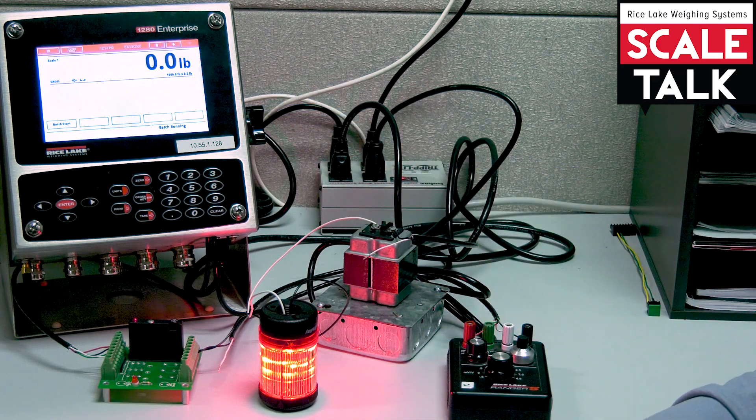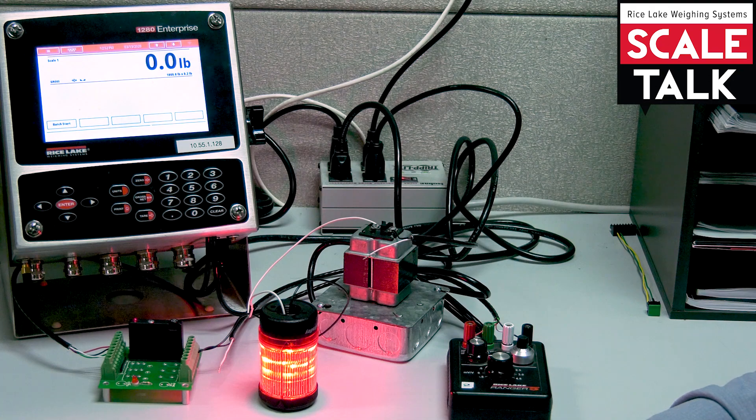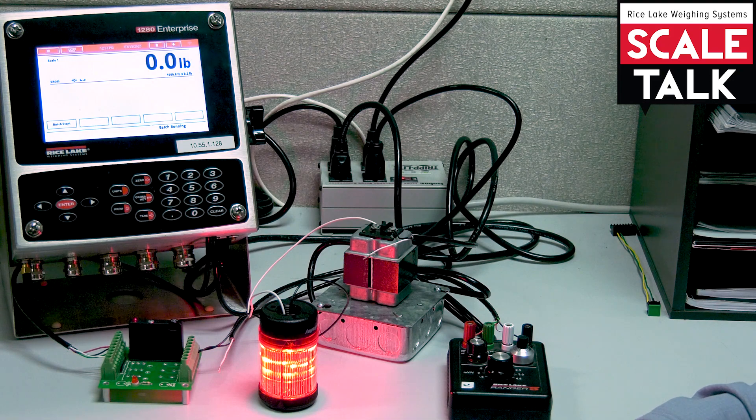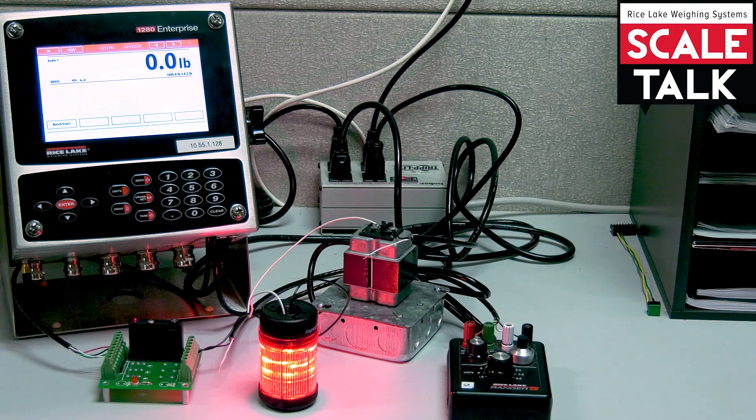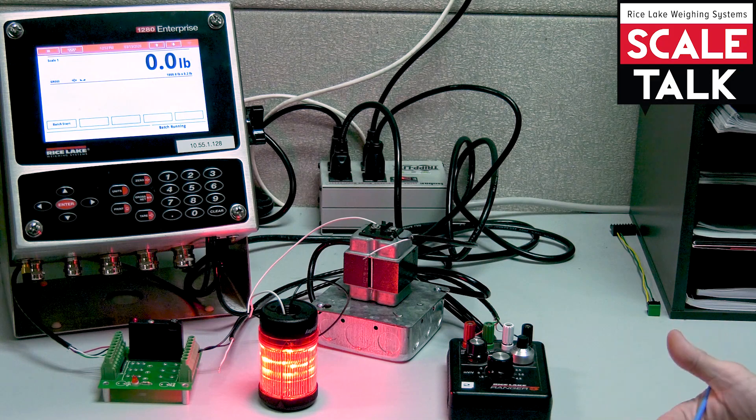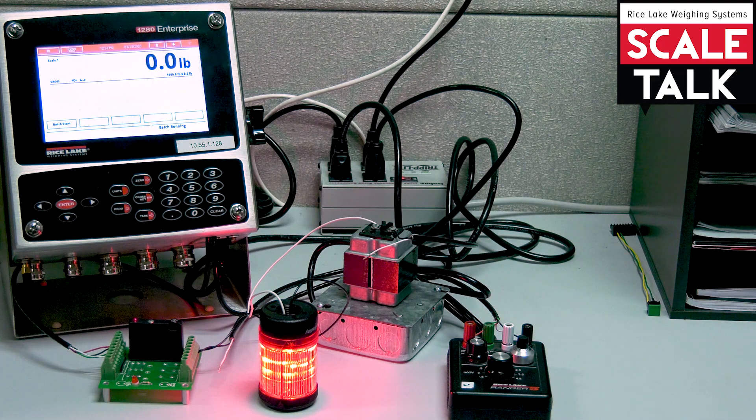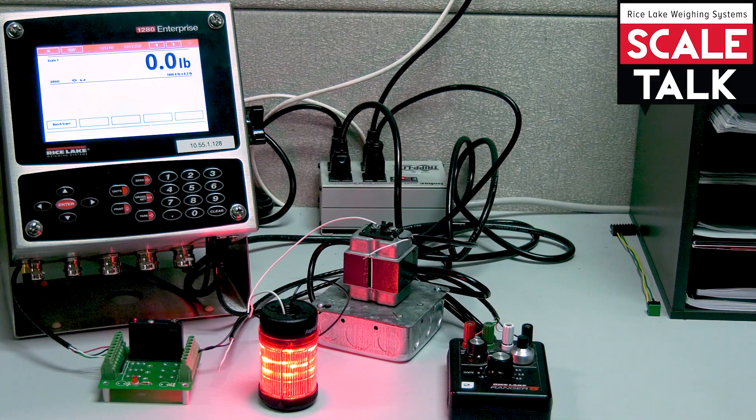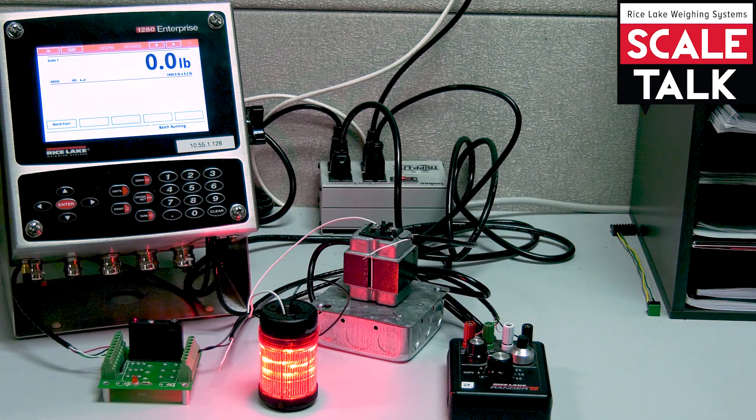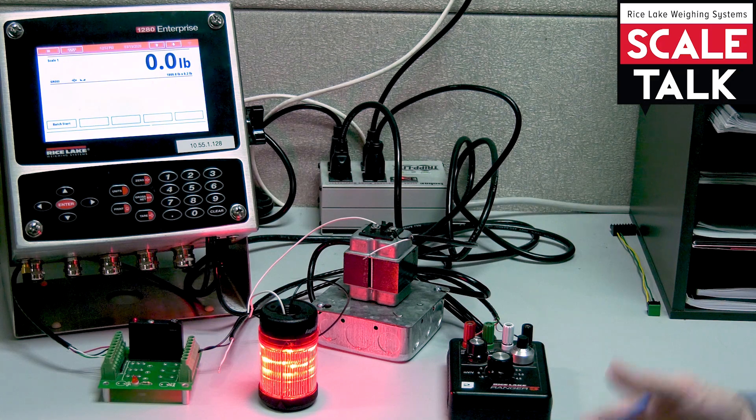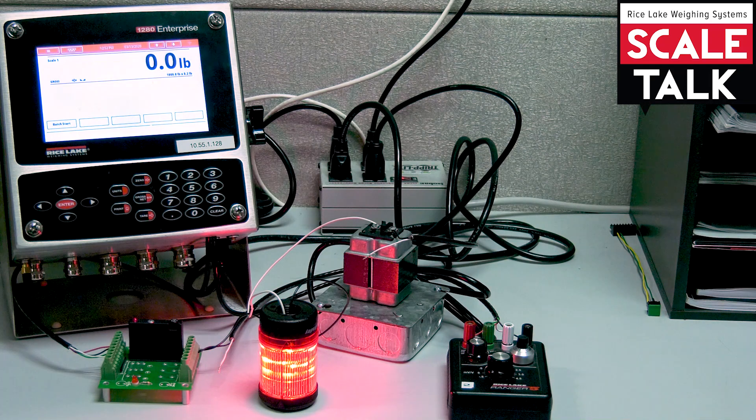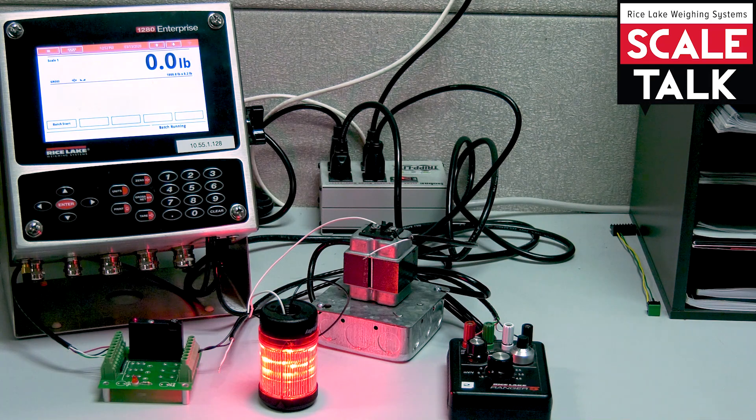Now you notice that the light came on right away. This is another very important difference between batching set points and free running set points. With a free running set point it was told to trip higher, so it didn't come on until we tripped higher and then it turned off when we were below. But as part of a batch routine, we're expecting that there's some kind of equipment like a valve or a chute that we want to open up and dispense some kind of product into a container. That's typically how this goes.